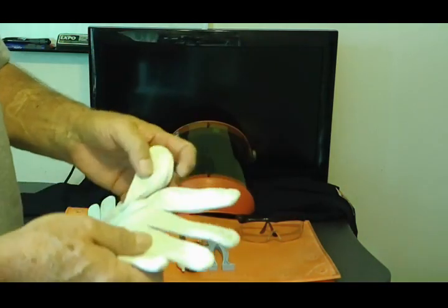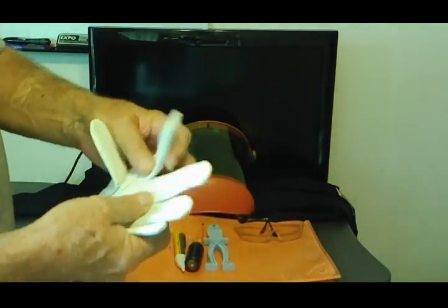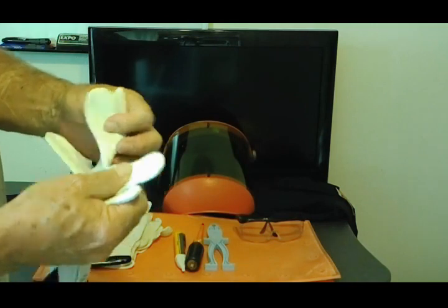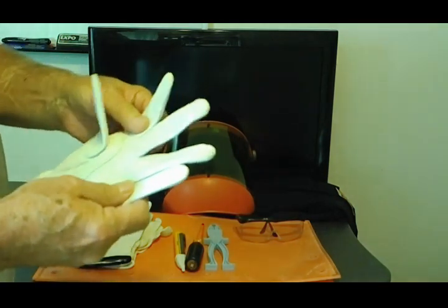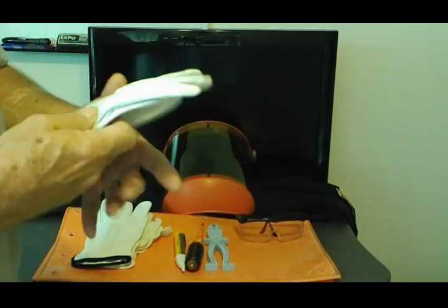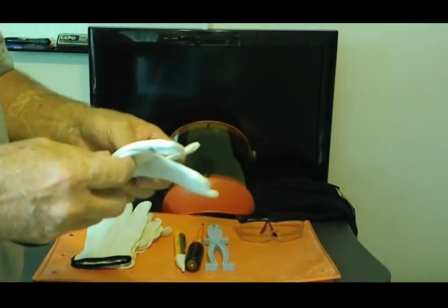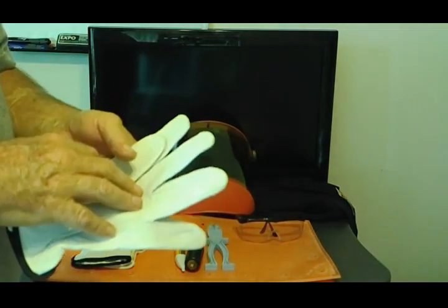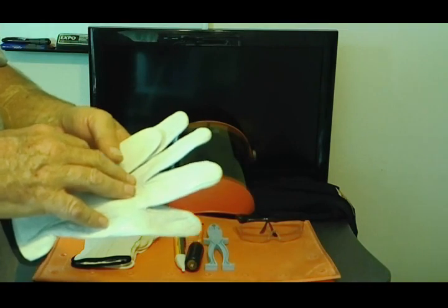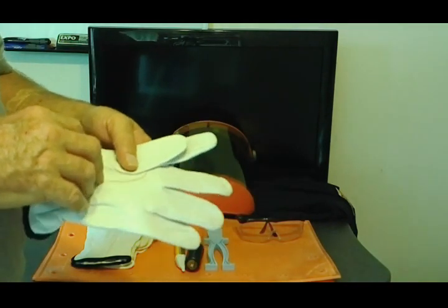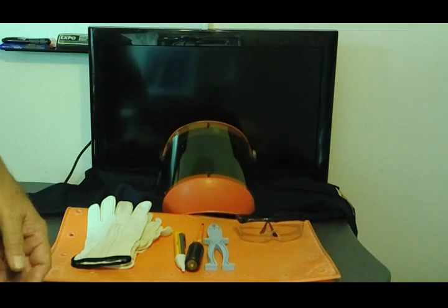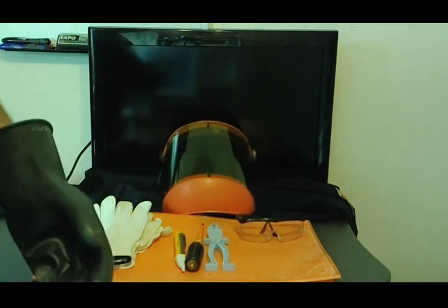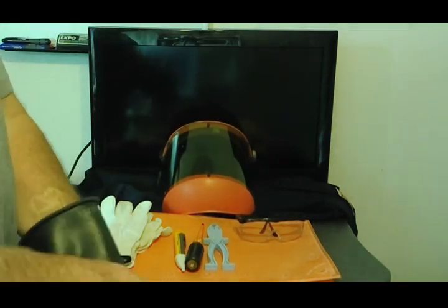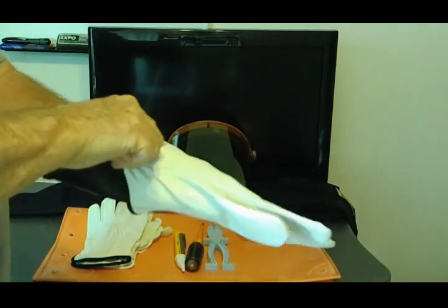Now, just like anything else, we have to inspect this glove before we put it on. Make sure there's no cuts, tears, stains, oil stains, sweat stains, no damage whatsoever on the gloves. It's the rubber glove that protects you from shock. It's the leather glove that protects the rubber glove. So right there, we put the leather glove over the rubber glove.